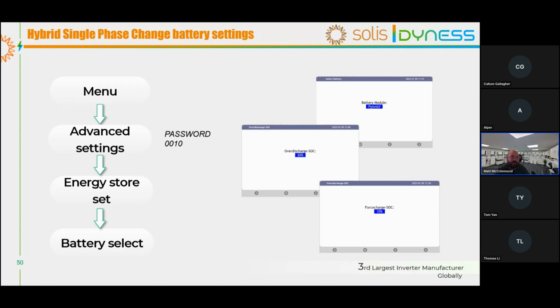So there's actually technically three values that you can in your head think about with your battery, but for setting up purely the battery, we need to figure out how much of the battery we want to be able to use. So if we look at the data sheet for Dyness, for example, and they said we want you to work within 100% and 10%, then you can set it to 100 and then overdischarge SOC at 20% or 10%. By default, it's always set at 20%. So that means that in normal operation between 100% and 20%, it will just oscillate. So it will charge the battery full to 100%, then discharge to 20%.